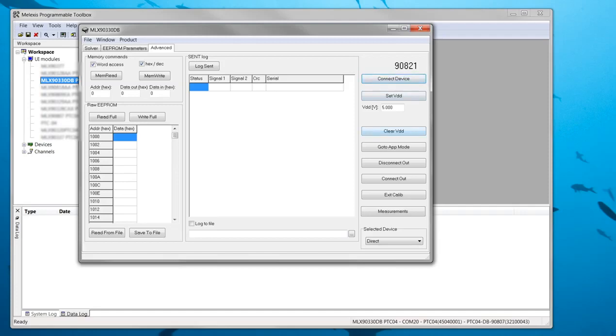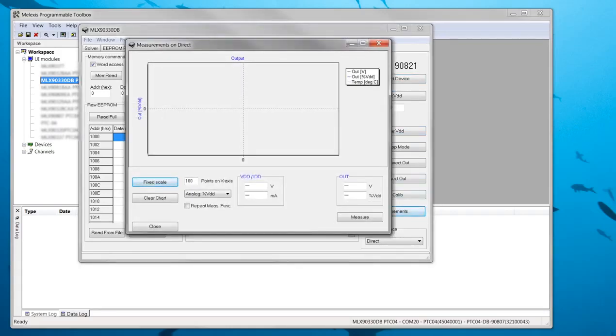The first three are the most important. Connect device does a communication test with a product. Set VDD sets the supply voltage to the desired level, and clear VDD resets the supply voltage to 0 volt to reset the connected device. The measurements button at the bottom opens a separate window where you can plot the pressure output over time.